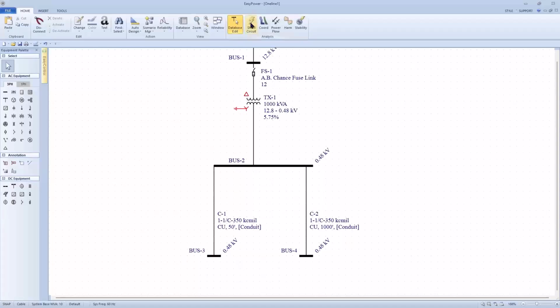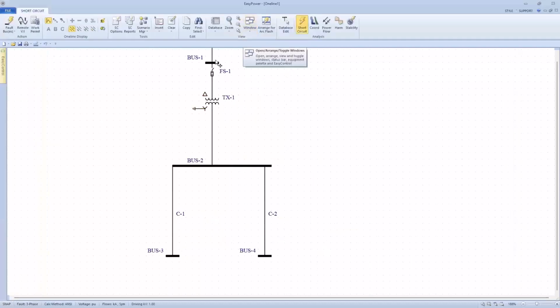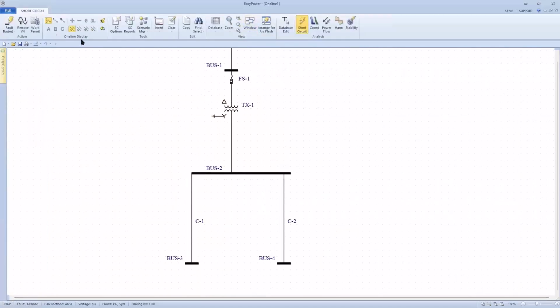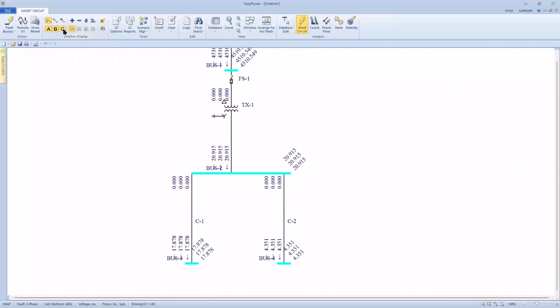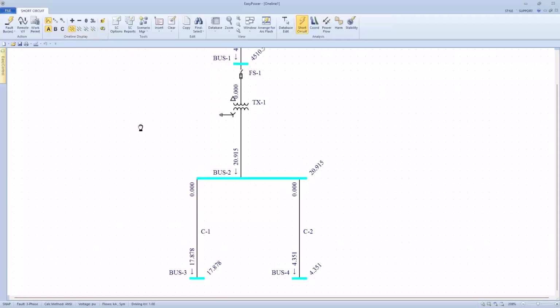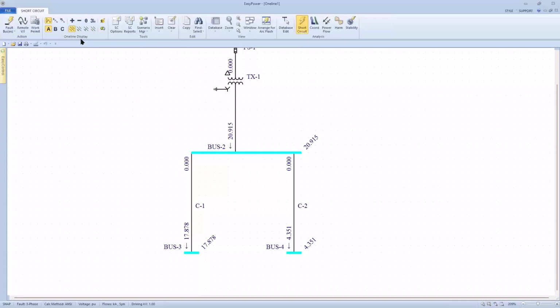So now I'm ready to go to short circuit focus, and as I do so, I get a clean one-line diagram. Electrician said, okay, the first thing we want to do is look at a half cycle. I'm up here on the top row on the left. Half cycle, three-phase bolted fault. And we're going to fault all the buses with a lightning bolt on the far left. And as we do so, we're looking only at the A phase. We can look at A, B, and C phase, but because they're all the same, it's a bolted fault, they're going to have the same magnitude. So we'll just stay involved with our A phase to reduce the clutter.